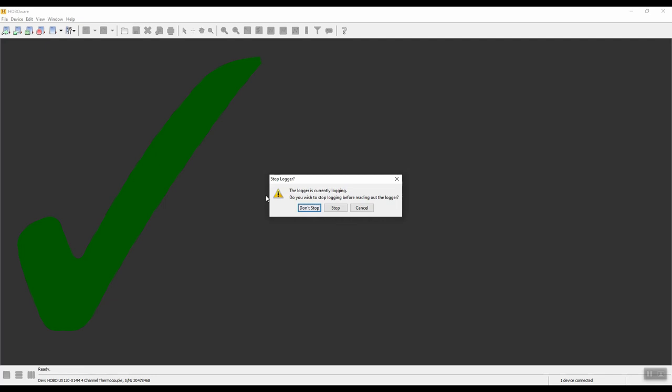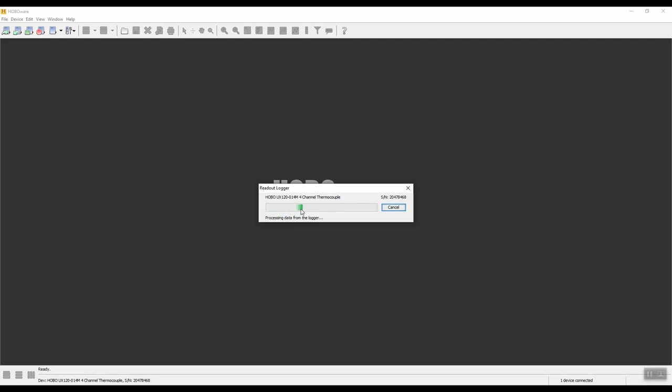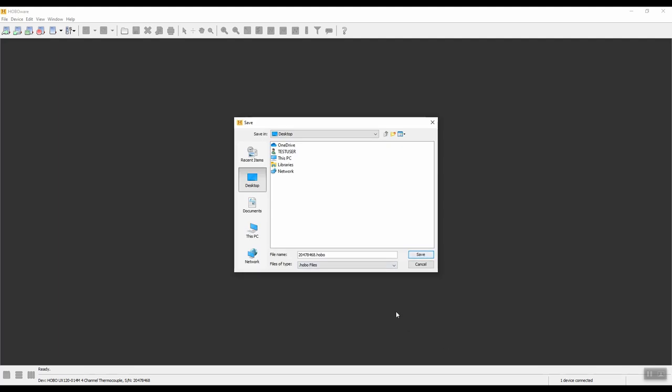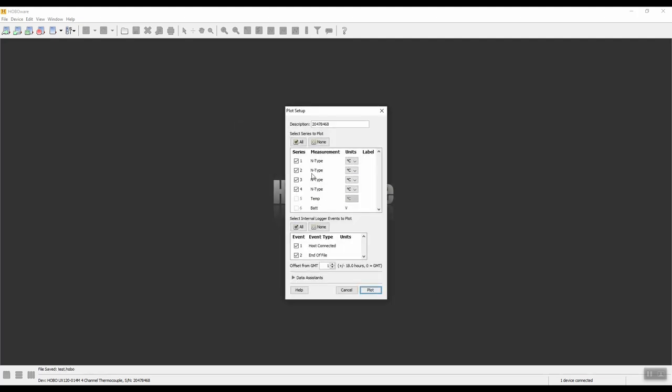It will ask you that the logger is currently logging. Do you wish to stop logging before reading out the logger? If you're not going to use the logger for a while, click on stop. But if you're going to carry on using the logger shortly after, click on don't stop. It will ask you to save the data and choose a destination. We'll go to documents and call it test, then click on save. It will show you the channels that you have enabled. You can deselect some if you wanted to, but we'll leave them all selected and click on plot.